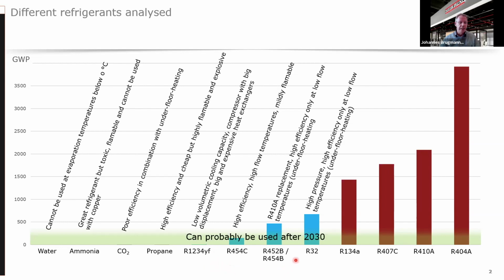Then we have these HFOs. There is R454C and R455A. It's not written here, but it's also one of these refrigerants below 150 and with very high efficiencies. And it's an A2L, so it might be flammable. And the main reason, the beauty of these refrigerants, is that they are below 150 in the GWP.